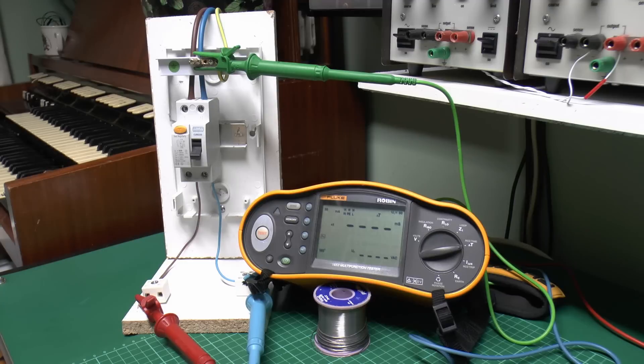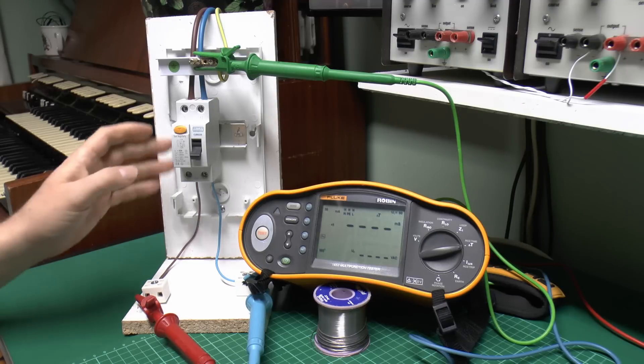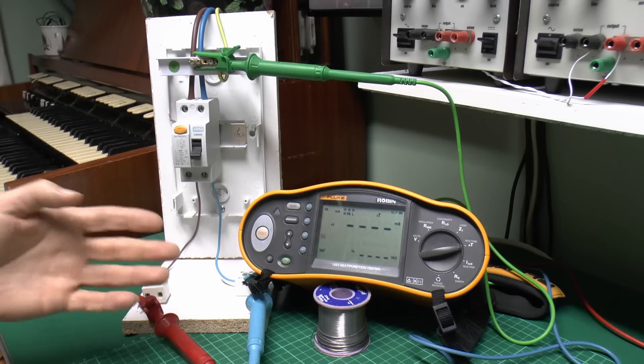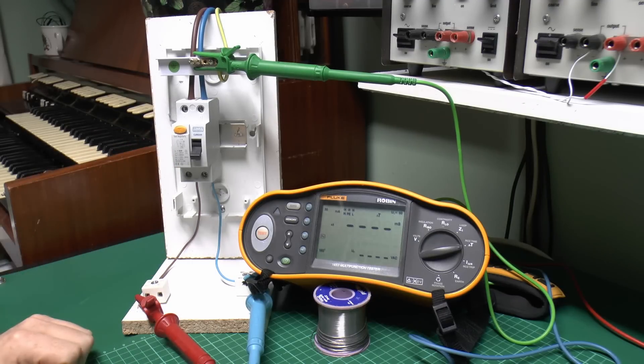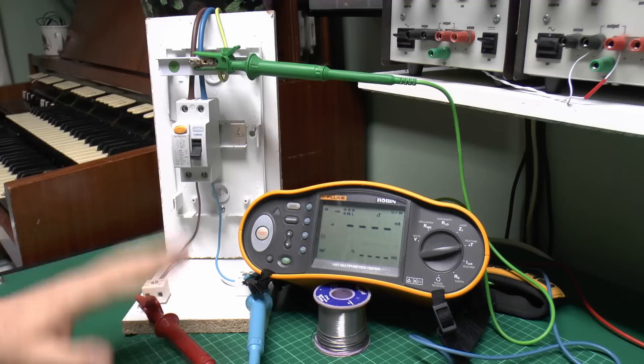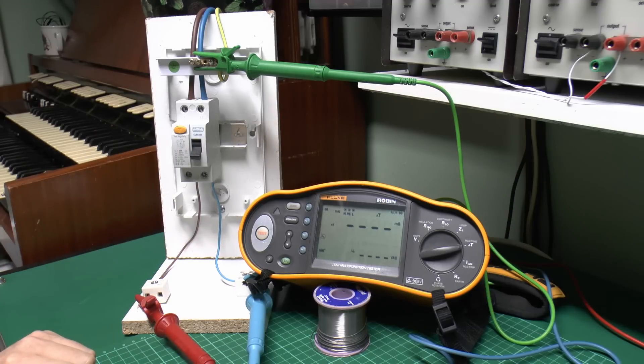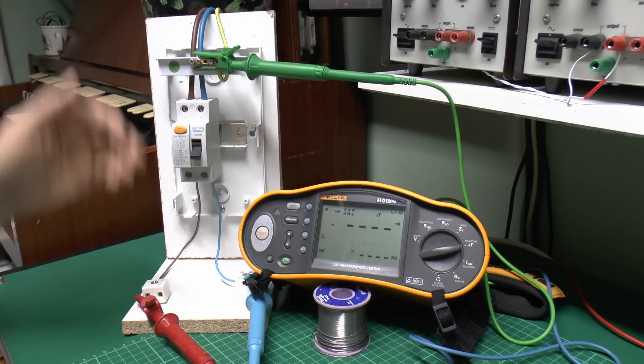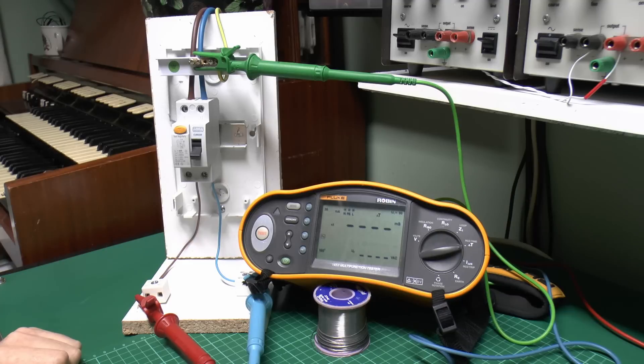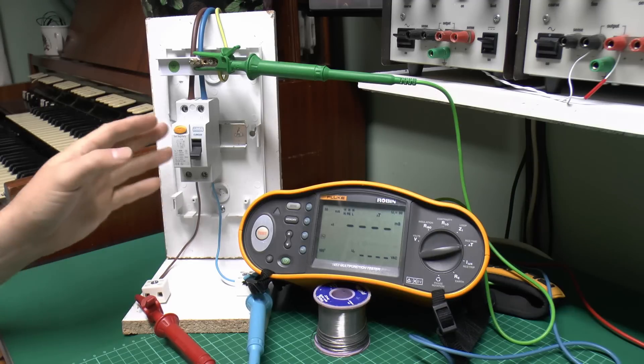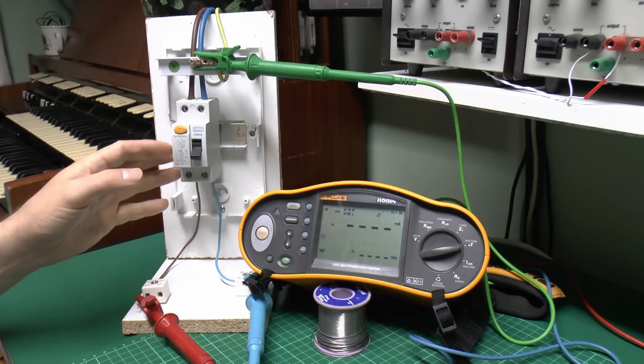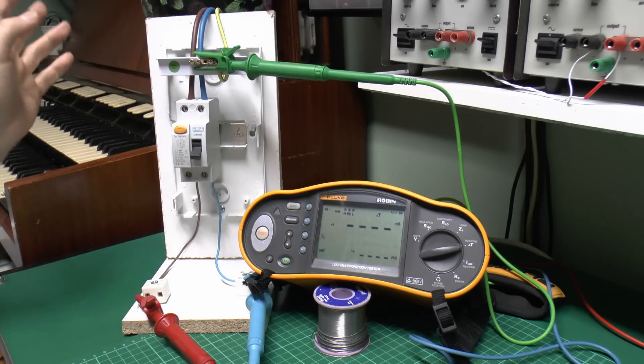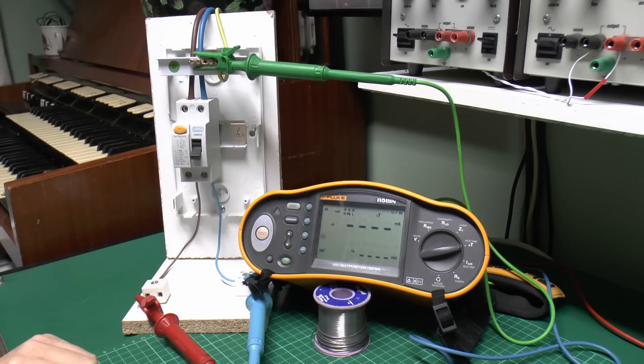Now in the majority of installations, there should only be a single RCD covering a particular circuit or set of circuits, and for that this particular test setup is absolutely fine. In some cases there will be another RCD installed on the supply side of the one you're testing, but normally that should be a time-delayed variety, so that when testing this one or if a fault occurs here, it doesn't actually trip the other one further upstream as well.